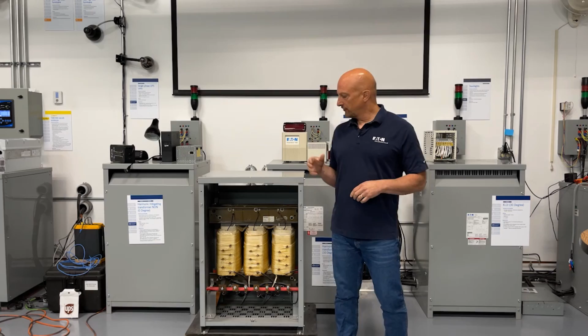So to get to the calculations that we need for a transformer like this, we want to think about full load amps on the primary, full load amps on the secondary, breaker sizing for primary and secondary, and then also fault current on the secondary. How are we going to get that information? Well, what we're going to do is we're going to go up to the nameplates of these transformers and we're going to find out the information that we're going to need to plug into our equations to calculate those values. Let's take a look at some actual transformers and see the ones that we're going to use in our calculations.